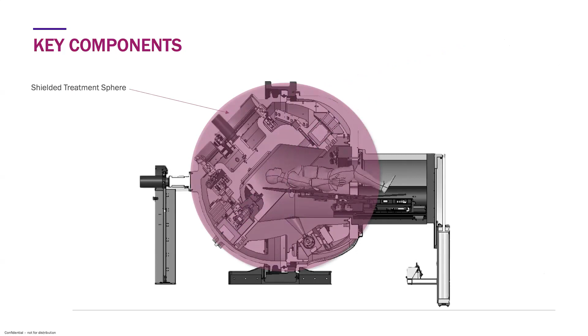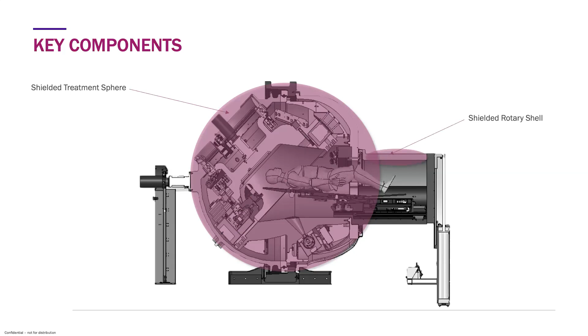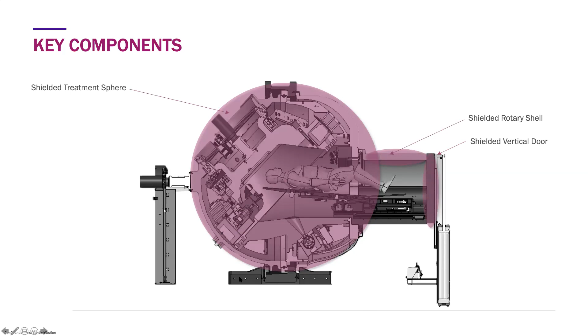And then all these mechanical elements are rotated in this large treatment sphere, which support the treatment components, such as your linear accelerators, such as your wave guides, such as your KV imagers, such as your mega voltage detector. And we'll go through these one by one. But they contain the radiation within this treatment sphere, allowing us to make this self-shielded. And there's also this rotary shell and door, all of which then contain the emitted radiation within this device, allowing the operator to sit right next to the patient treatment. And again, I repeat, the device opens up inside the apparatus, keeping this from being a claustrophobic experience.